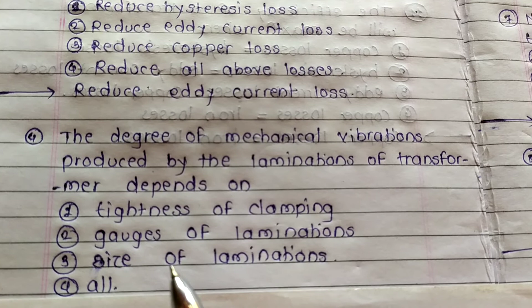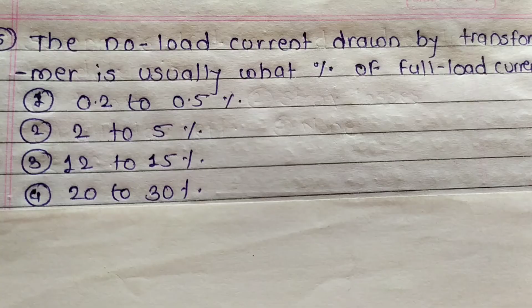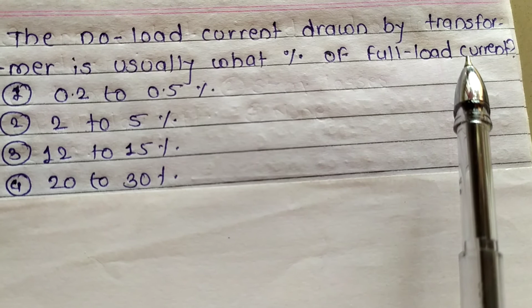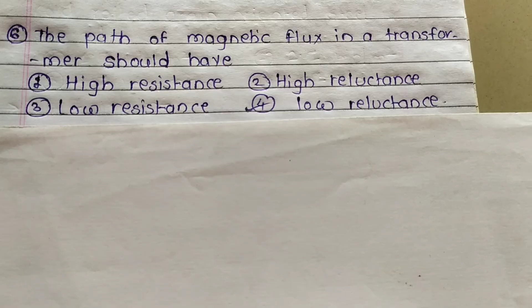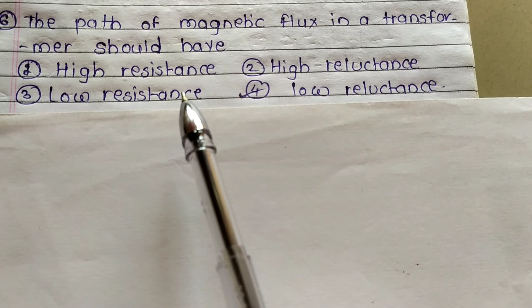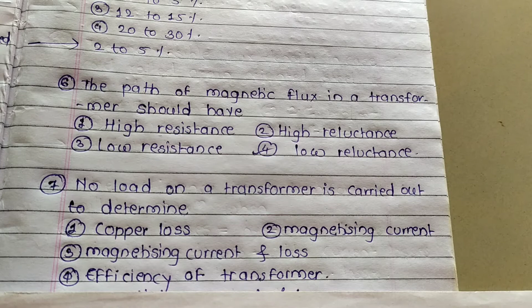The degree of mechanical vibrations produced by the laminations of a transformer depends on tightness of clamping, gauges of laminations, size of laminations, or all. The answer is all. The no load current drawn by transformer is usually what percent of a full load current? The answer is 2 to 5%. The path of magnetic flux in a transformer should have high resistance, high reluctance, low resistance, low reluctance. The answer is low reluctance.